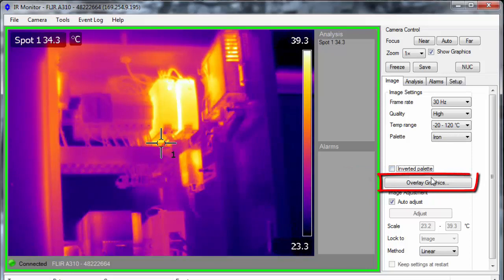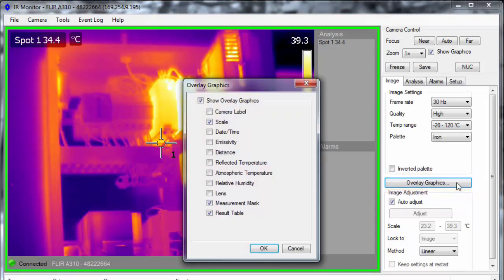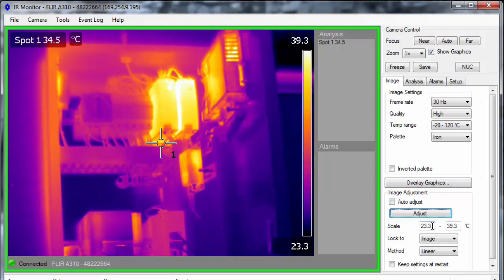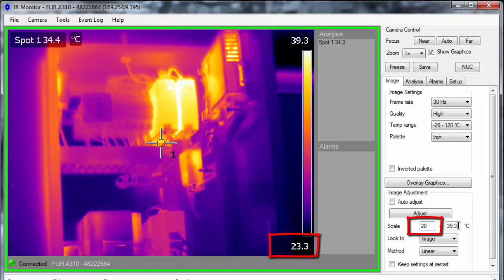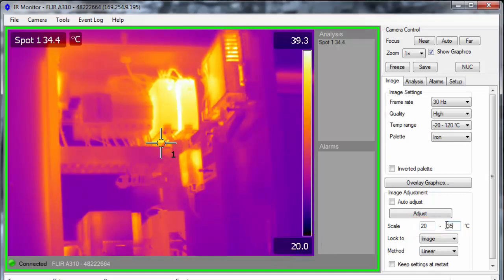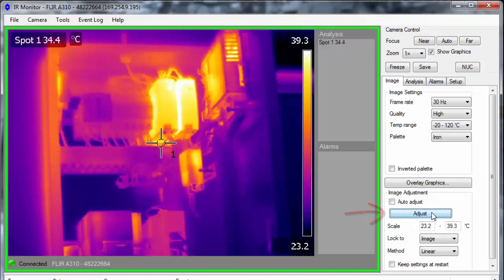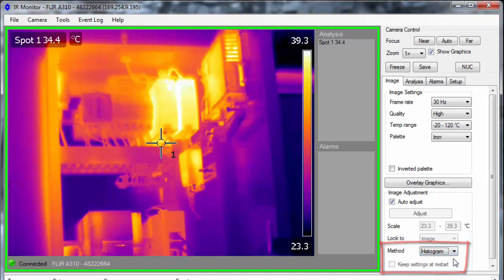Click Overlay Graphics to select what labels will be displayed on the camera image. The image span and level are set to auto adjust by default. By unchecking this option, you will be able to manually set the lower and upper limits of the scale. The Adjust button does a single automatic adjust based on the scene temperature, adjusting the lower and upper limits and leaving the camera on manual adjust mode. The colorization method can be switched between linear and histogram, but histogram only works when the auto adjust is active.